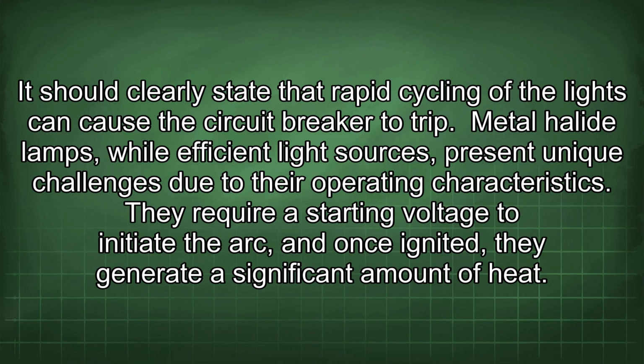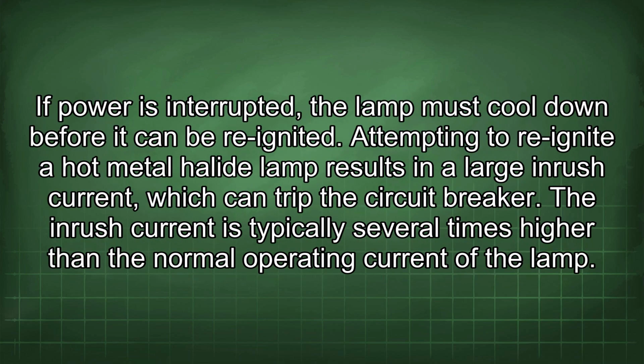Metal halide lamps, while efficient light sources, present unique challenges due to their operating characteristics. They require a starting voltage to initiate the arc, and once ignited, they generate a significant amount of heat. If power is interrupted, the lamp must cool down before it can be reignited. Attempting to reignite a hot metal halide lamp results in a large inrush current, which can trip the circuit breaker.